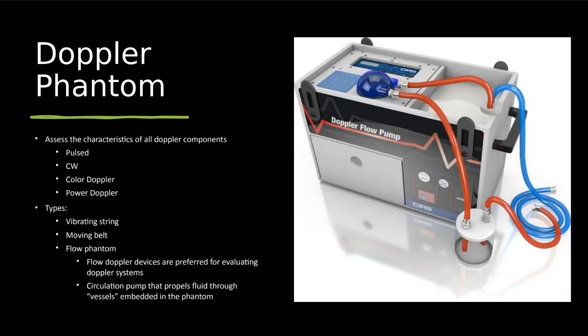Next is going to be a Doppler phantom. We actually had one of these laying around and it was extremely heavy. I don't know how they carry this from facility to facility, but this is going to help us evaluate the Doppler settings. So the color Doppler, continuous wave, pulse wave Doppler, anything that evaluates the movement of something is going to be done with the Doppler phantom. It does so by having these vibrating strings in the phantom, and it mocks that movement of usually fluid in the body. So again, we're evaluating all of the Doppler components of our system.